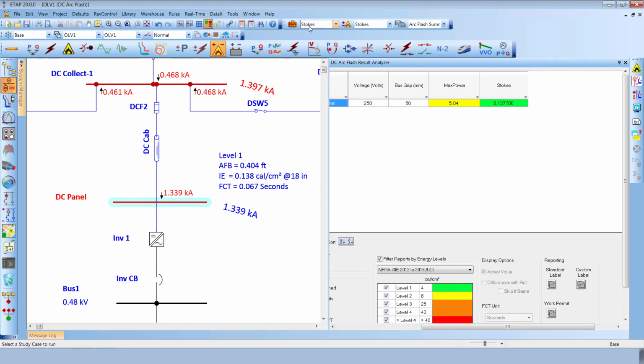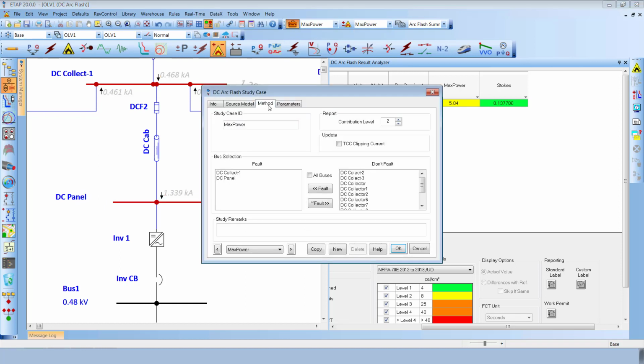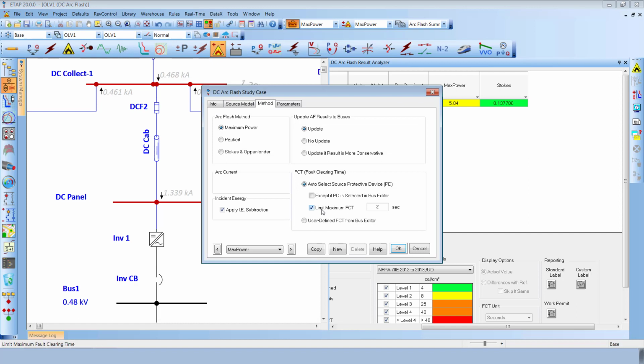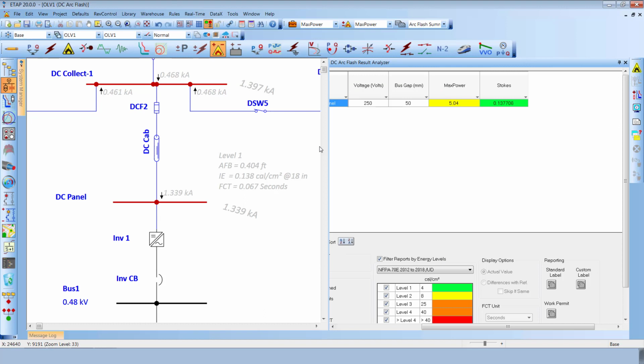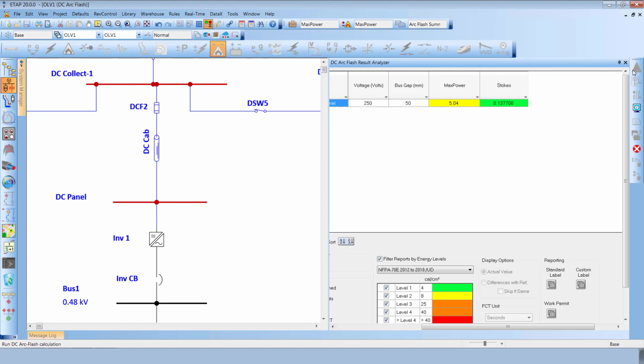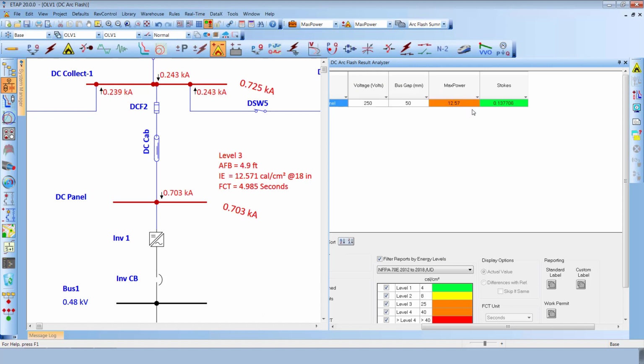Now the maximum power method with the 2-second rule removed originally gives you the overly conservative energy based on the actual operating time of the fuse DCF2. So the original reduction is actually from 12.57 calories to almost 0.14 calories per centimeter square for a given working distance for the same set of parameters that was given as input to the DC cabinets of the inverter side.